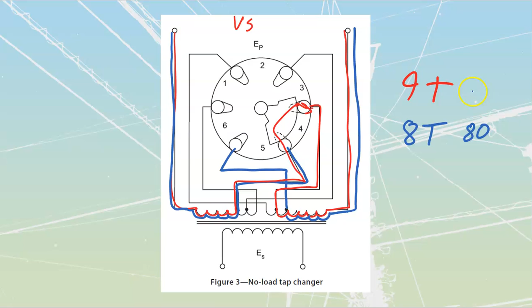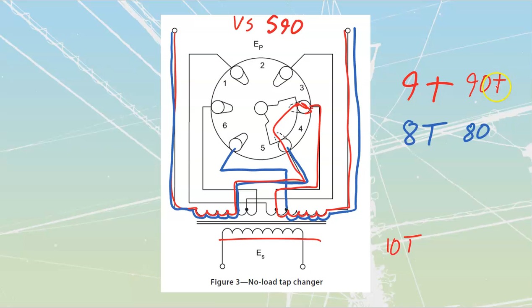If we take a look at our voltage value, whatever we place across here, let's place 590 volts across here. 590 volts over 90 turns gets me to 6.55 volts per turn, which means on the output side I'd have 65 volts across 10 turns - 10 times that same 6.55, so I'd end up with 65 out. I'll write that down, 65 out.